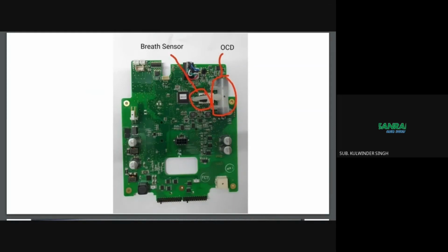Pulse mode machines have a built-in breath sensor. You can see on the PCB, this is an Inogen One G5 POC PCB, and the breath sensor is marked on it. Whenever the patient triggers or inhales, this breath sensor senses the breath. It needs nearly 0.12 kilopascals of negative pressure to be generated by the patient to initiate a breath.